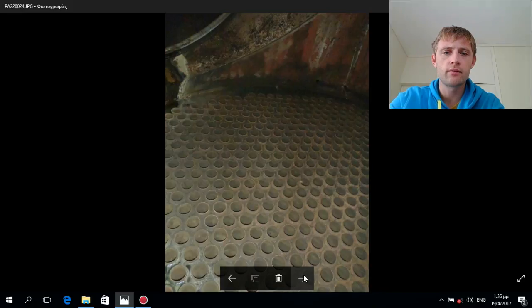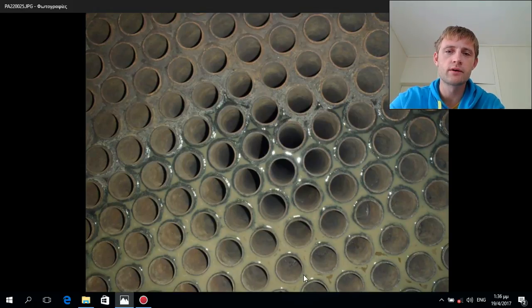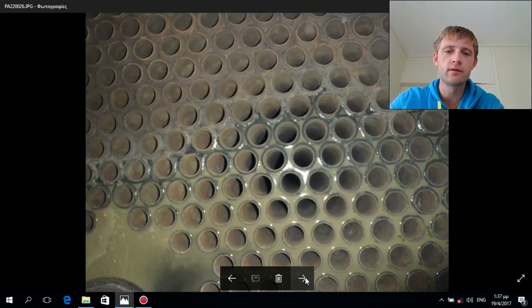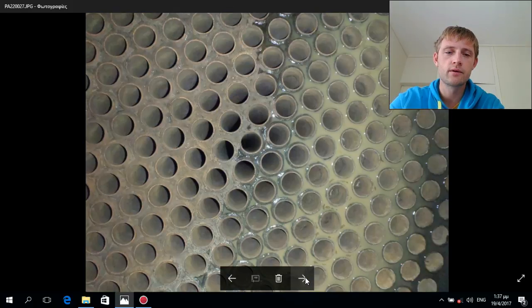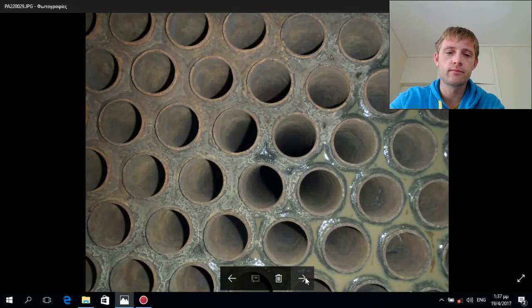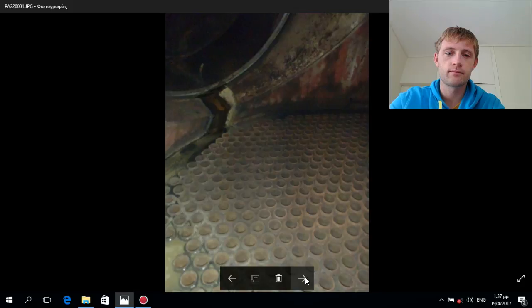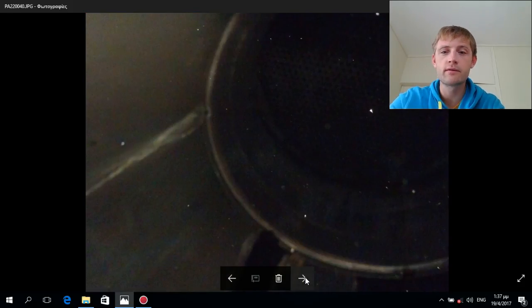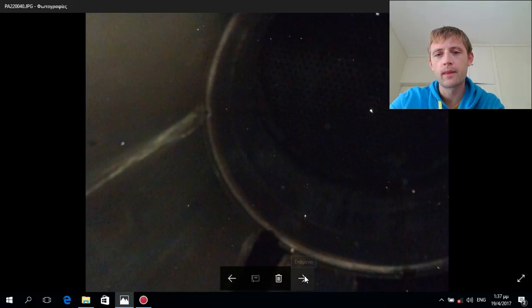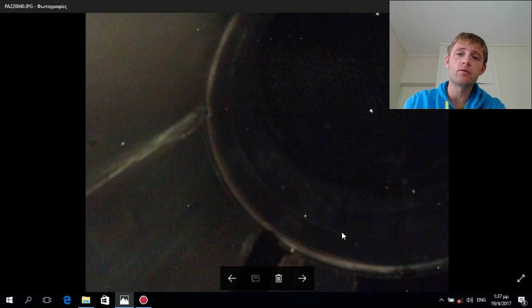Now the tubes - as you can see there is no any sediment, it's very clean. Also for this kind, three to four months, it's very good. You will not have any problem. Also if you are operating in tropical areas you will have steam, sure.